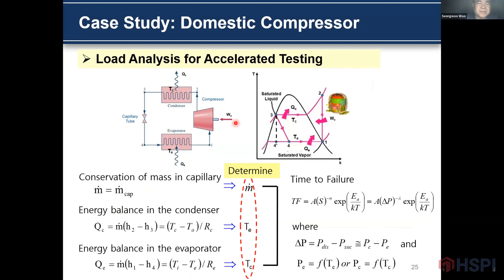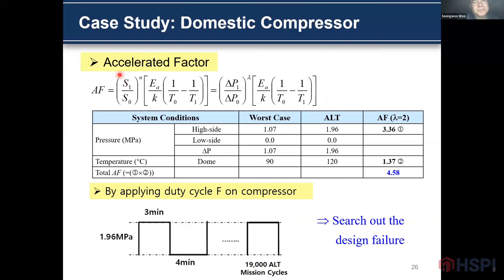This is the load analysis for the accelerated life testing. This is the vapor compression cycle and a test diagram. From conservation of mass in the expansion tube, and energy balance in the condenser and evaporator, we can determine the mass flow rate, evaporator temperature, and condenser conditions. Finally, we can define the time-to-failure model, which is dependent on the pressure difference and exponential temperature. The ALT acceleration factor depends on the ratio of the pressure difference and temperature difference. For the worst case, the pressure difference is 1.1. For ALT testing, the pressure difference is almost 2.0, giving an ALT factor of 3.3.